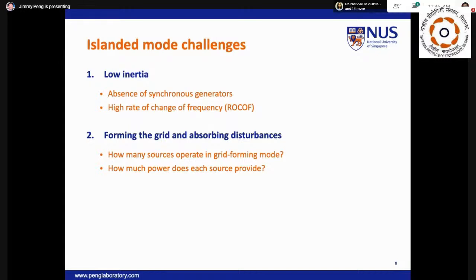Since a microgrid usually consists of multiple inverters, we will assign some of them to provide grid-forming functionalities. However, the capability of an inverter to regulate the entire microgrid is limited due to its rating. But assigning all inverters to operate in grid-forming mode may actually not be an attractive financial option. Note that the voltage and frequency regulations are the outcome of the disturbances, where controllers are attempting to restore equilibrium between the power generation and power consumption. Basically, the stability and control of a microgrid boils down to power sharing among the generation sources. The challenge is therefore to determine the fundamental nature of power sharing, which leads to the question of how the power imbalance within the microgrid should be managed by these grid-forming inverters.